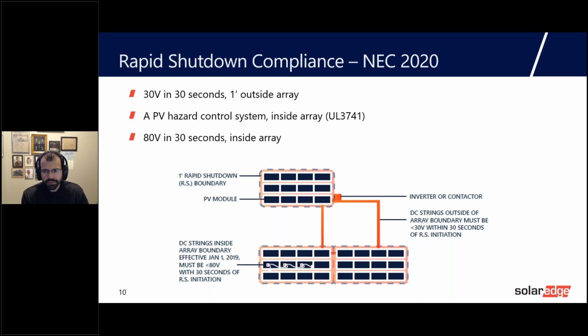Just starting from a standard perspective, a quick recap. The white paper that I talked about, which Jacob authored, goes from the NEC 2014 all the way to 2020, but let's start from 2020 for the sake of time. The 2020 National Electrical Code offers different options for rapid shutdown compliance regarding conductor control inside the array boundary. Upon rapid shutdown initiation, the system must achieve less than 30 volts within 30 seconds outside the array boundary. Inside the array, that's where the options come in: less than 80 volts within 30 seconds using a UL 1741 listed PV rapid shutdown system, or a listed or field labeled PV hazard control system as per UL 3741. So that's where the opening is allowed for 3741 systems.